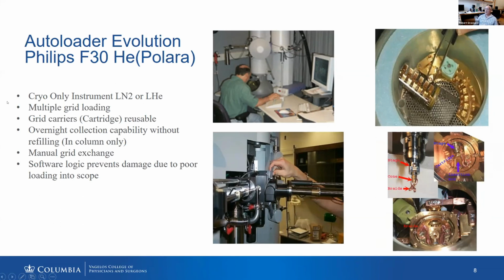Then with the advent of this, you could load multiple grids. You could put 6 grids. The grid cartridges were reusable, unlike the ones from the current systems, and you could get overnight data collection capacity instead of having the postdocs or the students stay overnight every 3 hours to fill up the dewars. The grid exchange was manual instead of clicking a button on the autoloader inventory panel, but it had software logic to prevent damage to the microscope. But like with anything else, if you didn't understand the system, it's tricky if there was a problem. And I'm sure that Wim can probably tell you the Polara has many of these tiny little wires that tend to break at the most inopportune time. And then if you don't know how to get around it, you're sort of stuck.